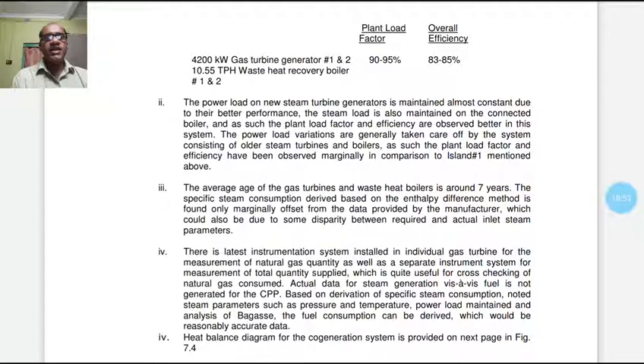There is an instrumentation system installed on each individual gas turbine for measurement of natural gas quantity, as well as a separate instrument system for measurement of total quantity supplied, which is quite useful for cross-checking the natural gas consumed. Actual data for steam generation via fuel is not generated for this plant. Based on derivation of specific steam consumption, noted steam parameters such as pressure and temperature, power load maintained and analysis of bagasse, the fuel consumption can be derived, which would be reasonably accurate data.